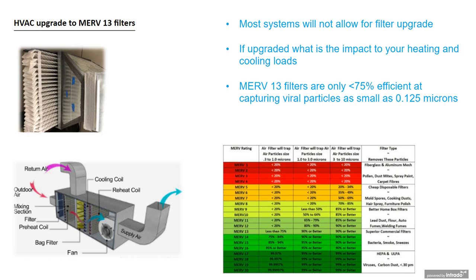But then we have to get into HEPA filters. HEPA filters start at MERV 17 filters and above. That's when we become 99.995% efficient and greater. So basically, the higher the MERV rated filter, the more efficient the filter is at capturing particles between 0.1 micron and 1 micron in size, and that's the danger zone. But again, just like the UV upper room UVGI, or just like the needlepoint bipolar ionization, this does not address room level mitigation. Again, if it's centralized and we don't have the proper filter in the system, those viruses could potentially be dispersed right back into the supply.